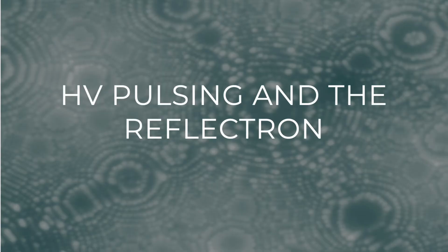So we can either pulse with high voltage pulsing, which has a number of idiosyncrasies that I'm going to discuss briefly, and this has led to the integration of reflectron lenses in the design of atom probes, and I'm going to briefly touch on the motivations and how this functions.